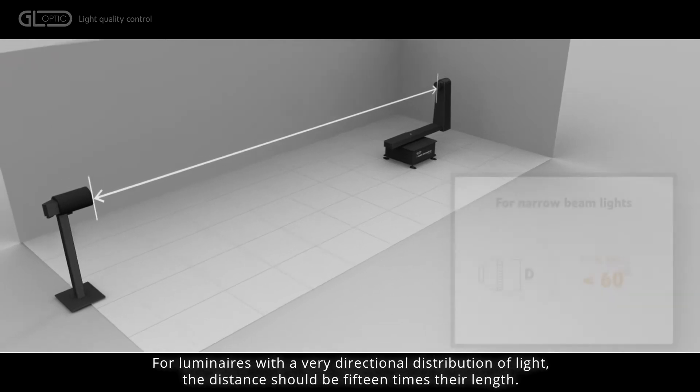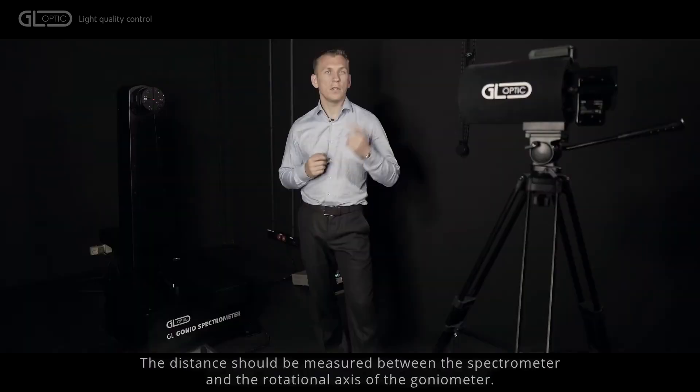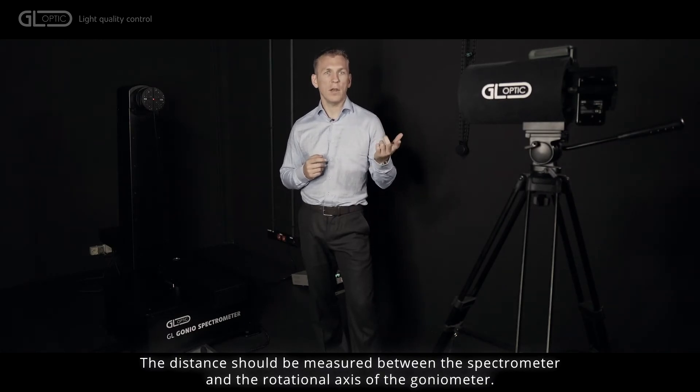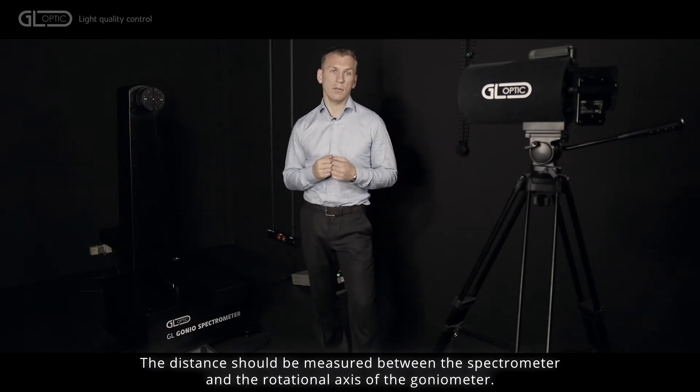For luminaires with very directional distribution of light, that distance should be fifteen times the length. The distance should be measured between the spectrometer and the rotational axis of the goniometer.